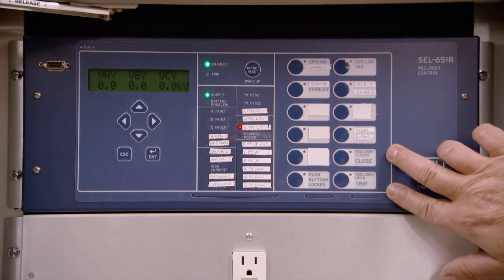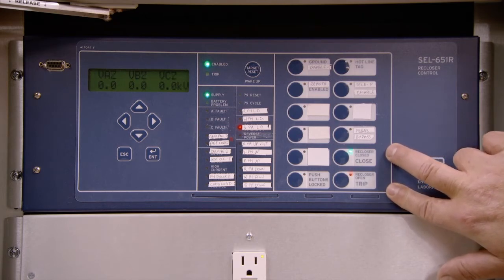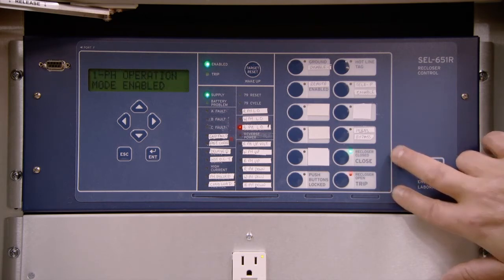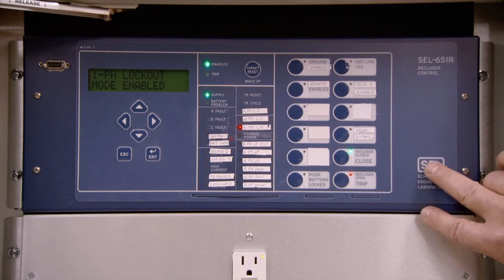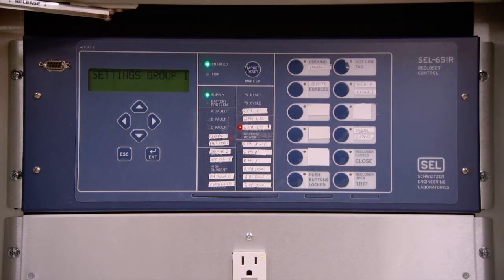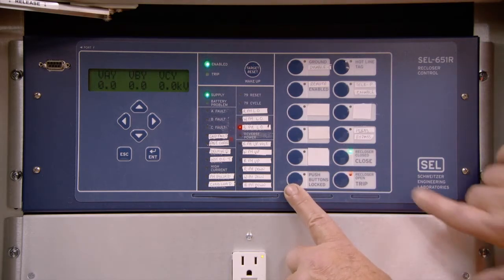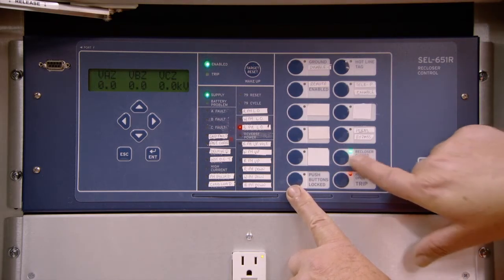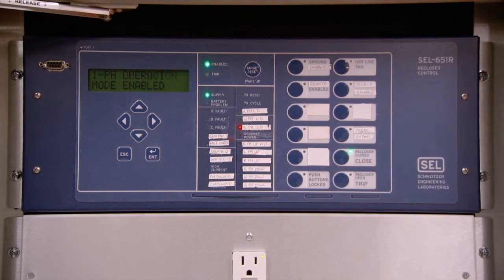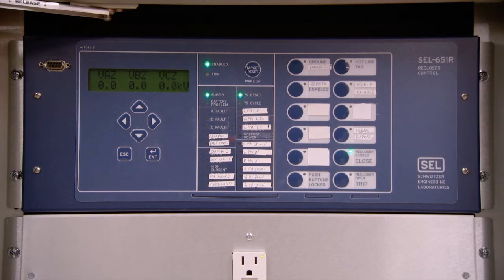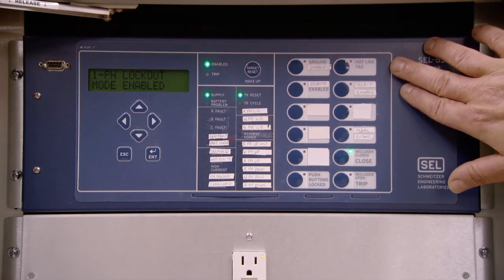The flashing trip and close buttons tell you that one of the breaker contacts is actually open. In that state, if you wish to close that open contact, you'll be required to perform the two-fingered operation. Push the push buttons locked button and the close button at the same time, and that will reclose the switch. If there were 1, 2, or 3 of the reclosers that had faulted open, they would indicate so across the left-hand side of the panel.